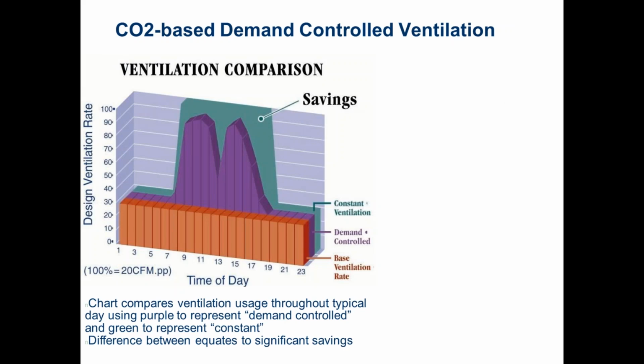Demand control ventilation is sometimes required, sometimes not, it just depends. If you don't know what demand control ventilation is, this is going to be the 60-second discussion of what is normally a 60-minute discussion. This graph here is from a building in Florida from years ago. I just keep using it over and over because I'm too lazy to make a new graph. This is time of day from midnight to midnight along the bottom, and this is percent of damper open, with the very top at 100 being 100% of the ventilation air. Not 100% of the economizer damper opening, but 100% of the code required ventilation air, which may only be 20 or 30% of the total CFM of the system.